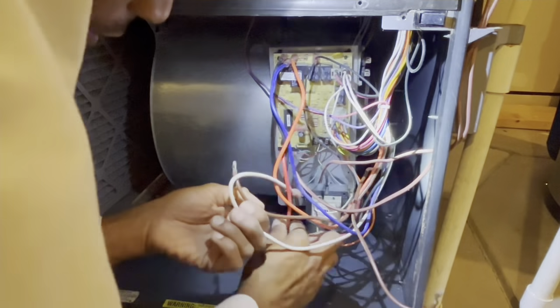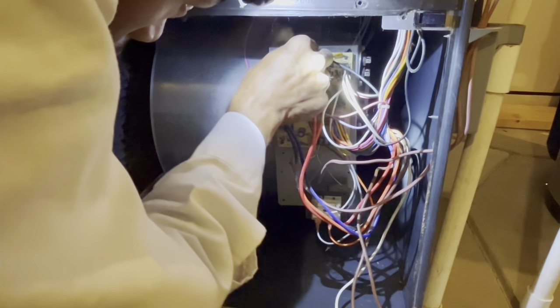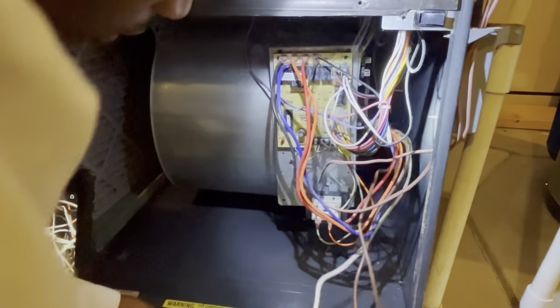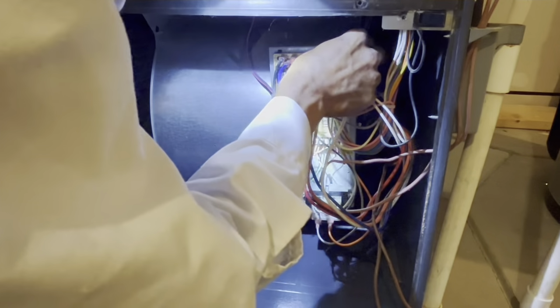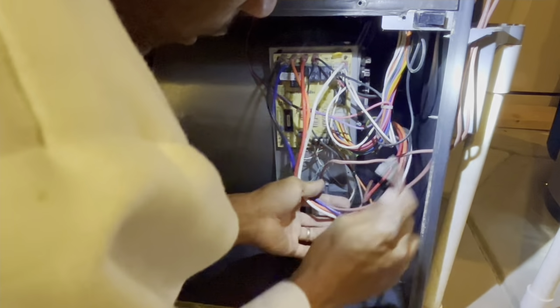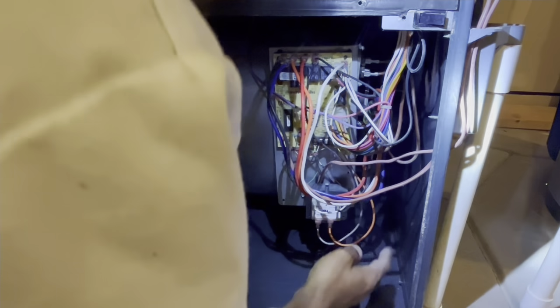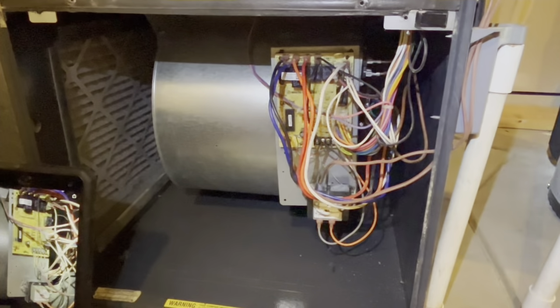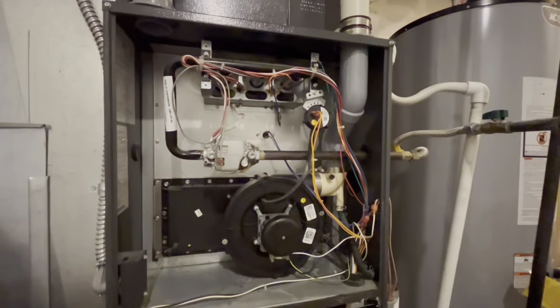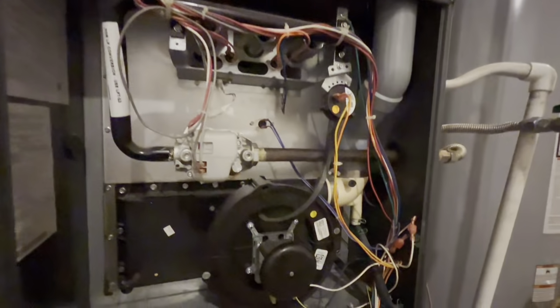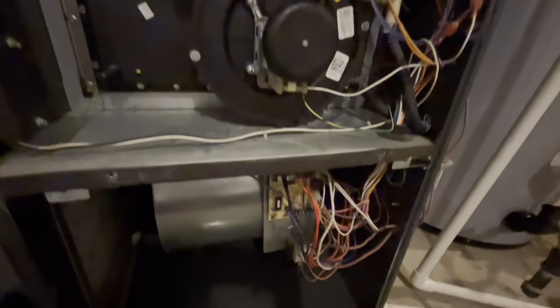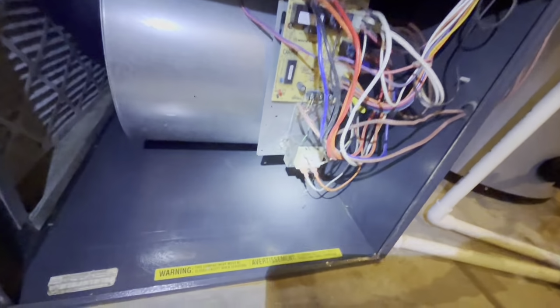Normally you have black going to cool, blue goes to heat, red and orange would be, or yellow could be a spare. That would go on spare or M1 and M2. And you always have a white neutral wire that provides 120 volts. And then you should have 2 brown wires that go to your blower motor capacitor in a sense. So sometimes it may be brown, and the other one may be brown and white. So it depends on your system.